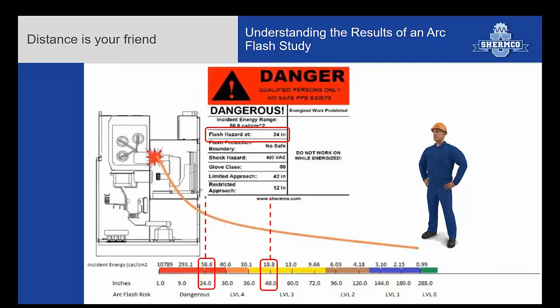If you're closer, as you can see on the bottom scale, the incident energy goes up dramatically. So if you get closer than that working distance, that should be a red flag to the worker as well. This gear is not dangerous gear. It is dangerous gear at 24 inches, if that makes sense.